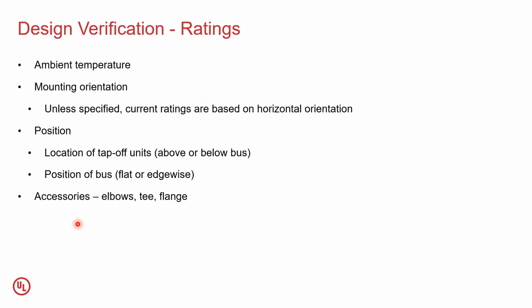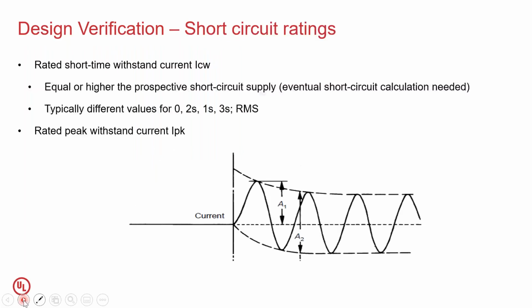A couple of other things to keep in mind are the location of tap-off units, whether above or below the bus, and the position, whether flatwise or edgewise. Also very important, because many of these are the weakest link in a busway system, are the elbows, T's and flanges. Unless you have all of them tested, if you're using any untested elbows or T's, it's quite possible that the whole product safety could get compromised. So that's something to bear in mind. About short circuit, I already discussed this. Short time withstand is always associated with the time.